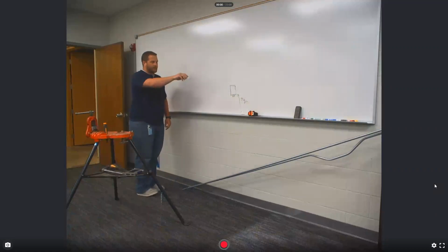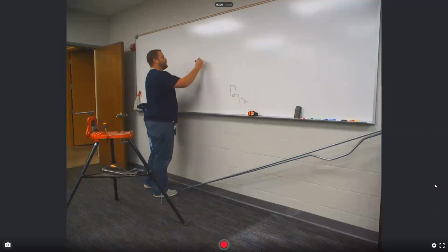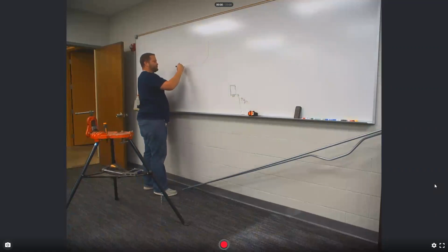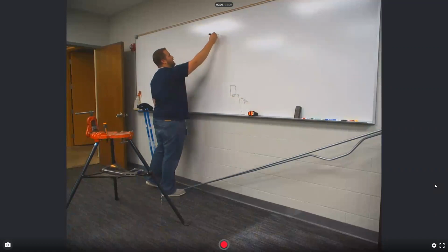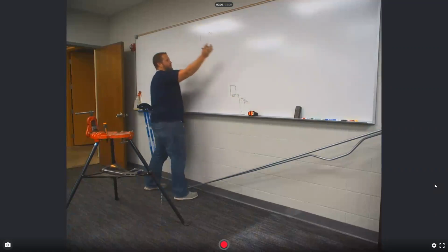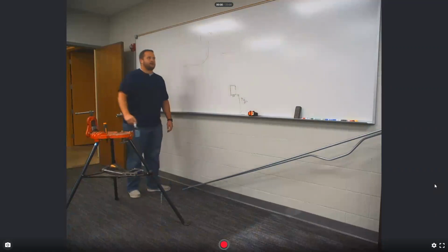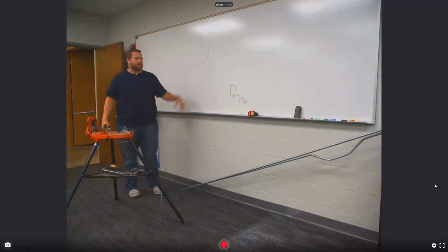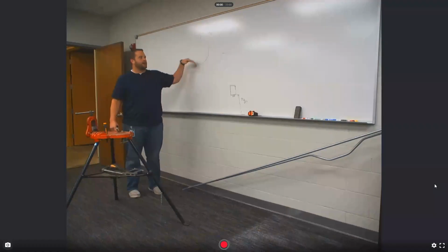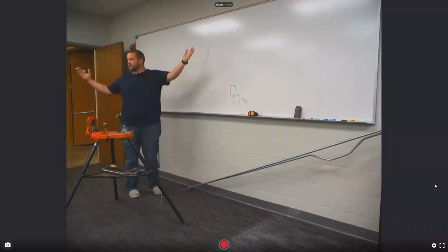when I put that thing in the bender and I end up putting this little radius on it, I can't take my flat piece of pipe and mark it at 9 3/8, because that would infer that when I'm done bending it, it looks like this. And our 90 is not going to look like that. It's going to have this little radius. So we need to know what the radius of that bend is going to take up. And that's actually called take up.